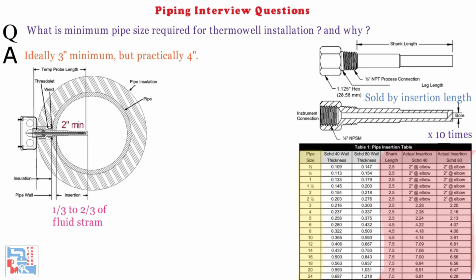Other guidelines recommend that the insertion length can be 10 times the thermowell tip diameter, or a minimum of 2 inches into the process. On the one hand, the longer the insertion length, the greater the chances that the thermowell will bend or suffer mechanical fatigue due to the process media's velocity. On the other hand, the shorter the insertion length, the greater the chances that users will see unreliable results due to poorer heat transfer. In summary, there is no one perfect stem length for a thermowell, but the goal is to balance the outcome.